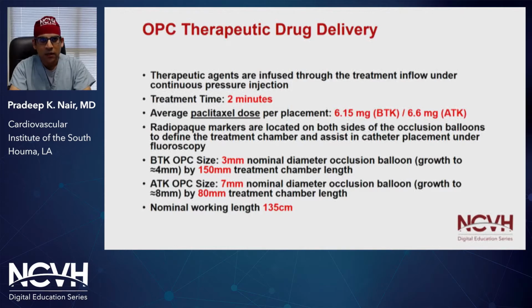So when we look at this drug delivery, the treatment time totals 2 minutes. We infuse the drug, in this case liquid paclitaxel, under continuous pressure injection. For the clinical trials and study, each dose and each placement of the OPC device delivered approximately 6 milligrams of paclitaxel. We have radiopaque markers on both sides of the occlusion balloon to define the treatment chamber and know where you're treating. The outer occlusion balloons have a 3 millimeter nominal diameter and can grow up to 4 millimeters. And there is a 150 millimeter treatment chamber length for the below-the-knee device.